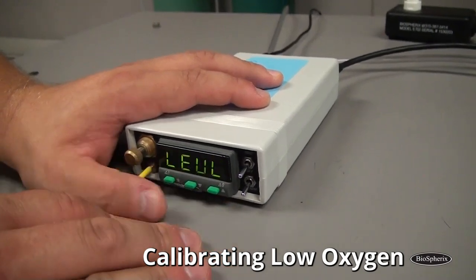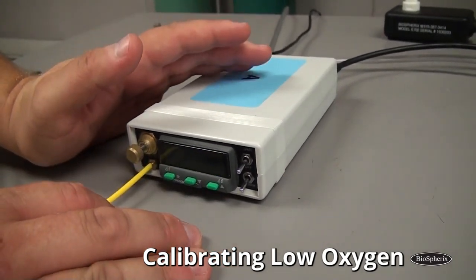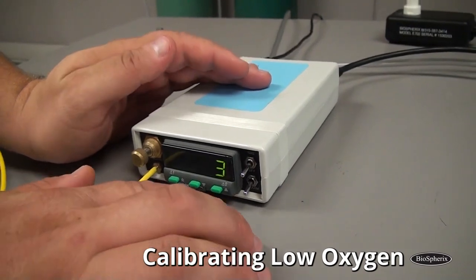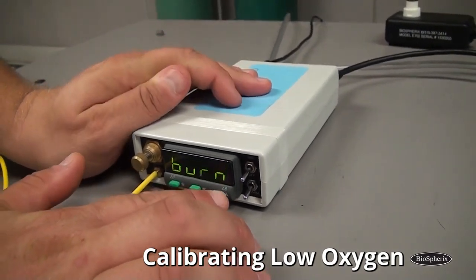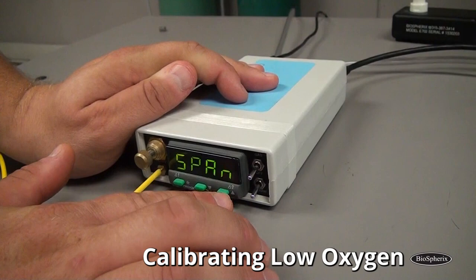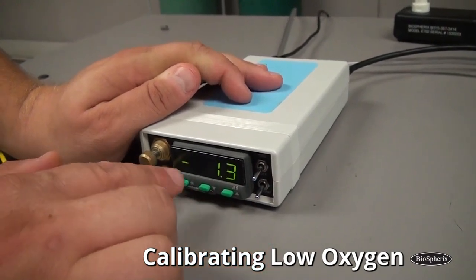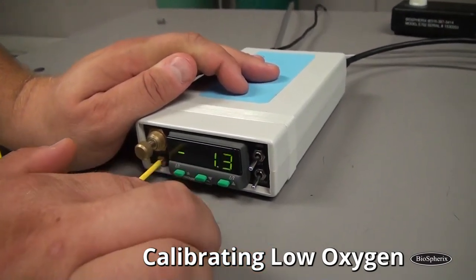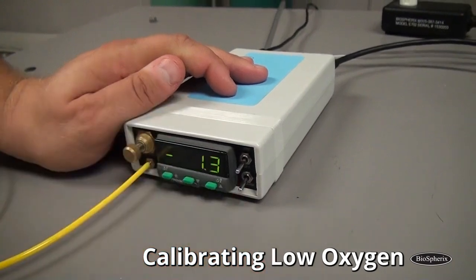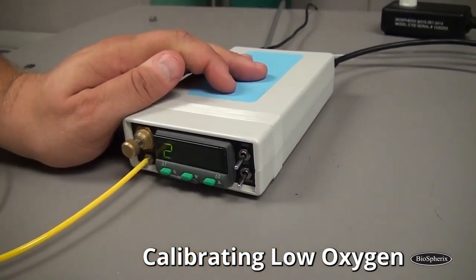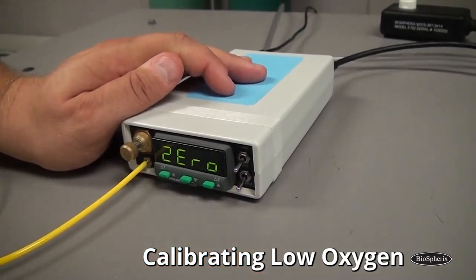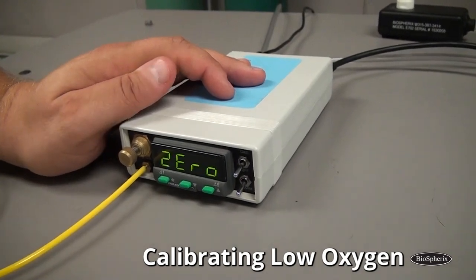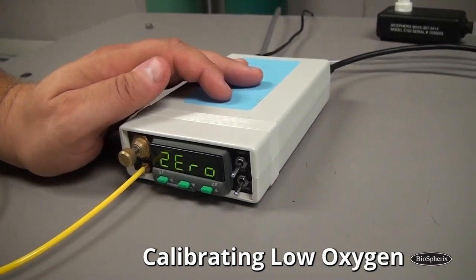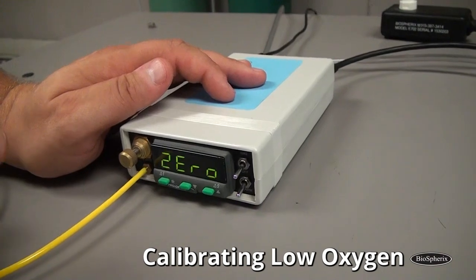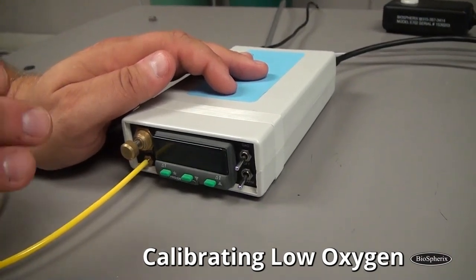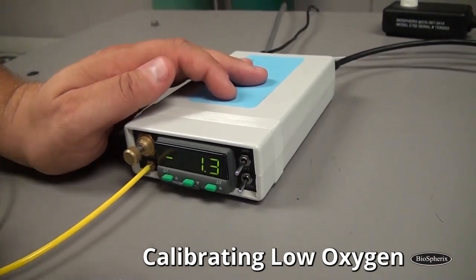So now I'm on level 3, and I want to navigate to 0. I just press up, and there it is, 0. It looks kind of strange, but that's 0. And it alternates with a calibration coefficient. And that number doesn't mean a whole lot. When we're done, I'll kind of explain. But whatever you were off from 0 by, you need to make that adjustment to this coefficient.